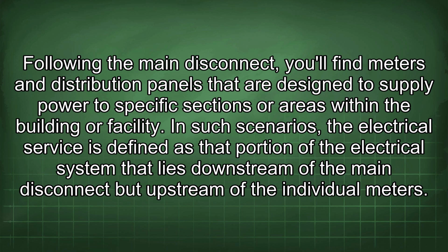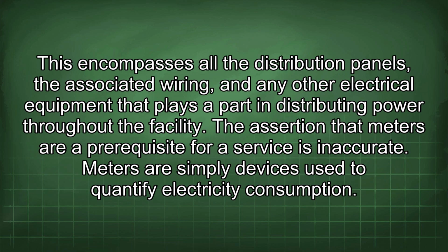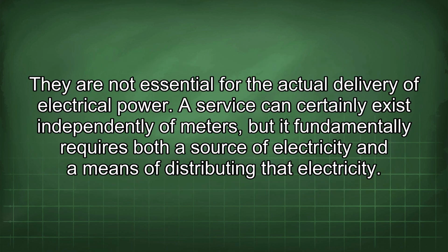In such scenarios, the electrical service is defined as that portion of the electrical system that lies downstream of the main disconnect but upstream of the individual meters. This encompasses all the distribution panels, the associated wiring, and any other electrical equipment that plays a part in distributing power throughout the facility. The assertion that meters are a prerequisite for a service is inaccurate. Meters are simply devices used to quantify electricity consumption. They are not essential for the actual delivery of electrical power.